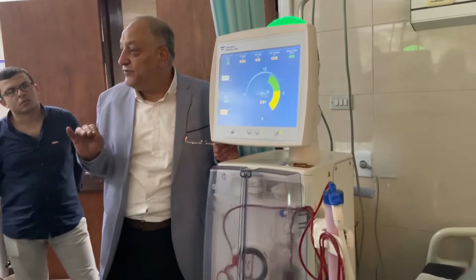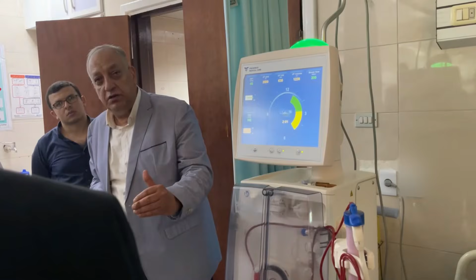The usual dose of hemodiafiltration is around 100 ml per minute substitution. And the blood flow, if it is only 300 ml per minute, so the filtration is 100 divided by 300, so the filtration fraction is 33%. Never go above 25 to 27. Above that means hemoconcentration. Some people like to say 20 maximum. Yes, 20 in pre-dilution is easy, but here it is difficult.